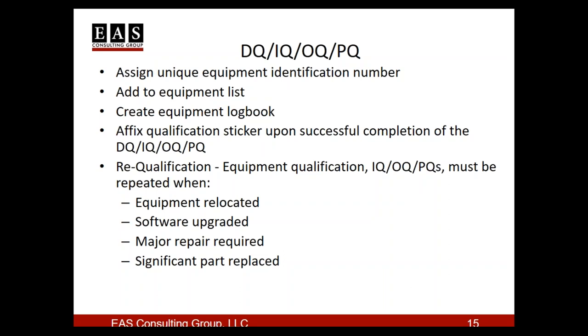Then we'll have to requalify the equipment. Now it wouldn't be a DQ, because if we've already done the DQ, that won't apply a second time around. But we may need to repeat the requalification if we relocate the equipment, upgrade the software, or if there's any major repair required. If it's a repair to a specific piece of equipment within a larger system, you may not have to requalify the entire system, just that section or piece. Or if there's a significant part replaced—there'll have to be an assessment by appropriately trained personnel to know what has to be repeated of the IQ, OQ, PQ process.